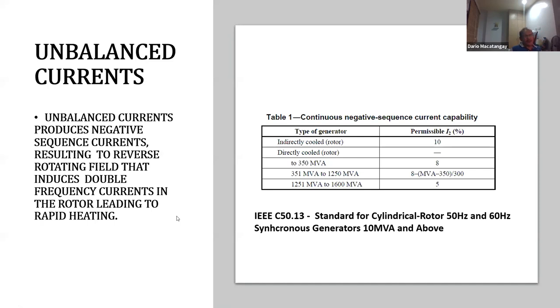And when you have unbalanced currents, you produce negative sequence current. Okay? During normal condition, the only sequence components that you have are positive sequence components. When you have an imbalance, then you produce negative sequence currents. That results in a reverse rotating field that induces double frequency currents in the rotor, leading to rapid heating. So that can cause rotor heating damage. Okay, that's unbalanced. Now, IEEE C50.13 has requirements on the manufacturer for the permissible negative sequence current, like 10% for an indirectly cooled rotor, and so on, okay?